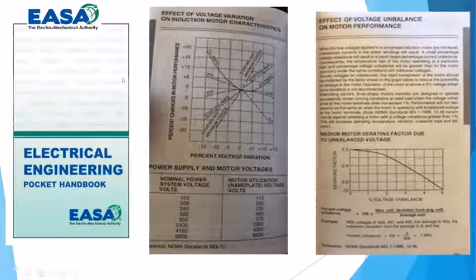And this is one area that I want to start with, about motor failure and why they're happening. One of the big areas is that the motors today are designed a lot closer to tolerance of total load, because then your power factor is better. But that's ideal application. And when you get out into a pumping world, and you have various transformers, you have Y or delta type power sources, open delta, what happens is those three legs feeding to the motor are not always balanced. And so this gives you the actual best derating factor, so you can maintain the life of those motors.